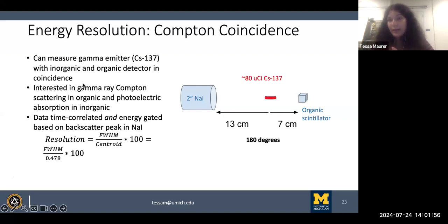But what they do have is really fast timing properties. And so that can be really important for you. Inorganic detectors are slow. And so if you're doing any kind of imaging or something like that, you're going to need as precise timing as you could possibly get. Actually, for PET scanners, getting slightly off topic here, but there's something called the 10 picosecond challenge, where they're trying to get down to a coincidence timing resolution of 10 picoseconds, because that'll transform how they do PET scans for you, and make it a lot better. And so fast timing, important.